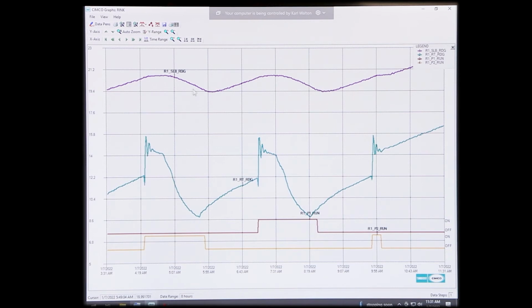If you notice here, when I move the mouse, if you look at the lower left corner of the screen, it says cursor all the way at the bottom. It shows a date and a time. I'm going to move down here, show you this area right here, okay? The bottom, all right? As I bring the mouse to the point of that temperature read, you look down the bottom left corner, it tells me it's at 19.35 degrees and exactly what date and what time, okay? So you can see when your highs and lows are. Remember I said I could tell when you were flooding and when you weren't?